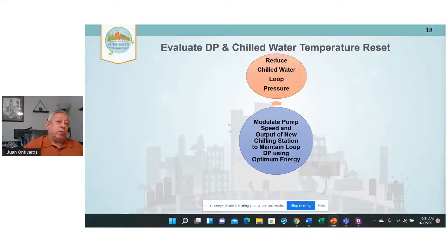So what we decided to do is reduce the chill water loop pressure. By that I mean you send water out, that's supply water, and you have return water coming back. What is the differential pressure between the two? We wanted to reduce the chill water loop pressure because I wanted to reduce pump horsepower. If you have too high a pressure in the supply, the control valves in your buildings cannot sustain the pressure. If it's too high a pressure, the valve lifts.